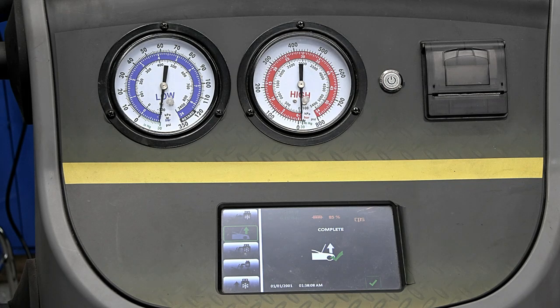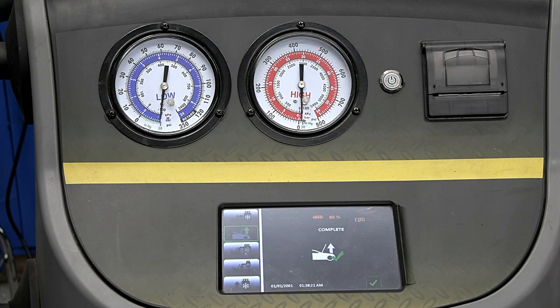Yeah, there's a couple. Is the CO2 better than traditional leak detectors, especially for detecting evaporators? Yes, CO2 is a smaller molecule, so it is way better. If you look at some of the videos I've done in the past, even in a class, I remember one where the guy's evaporator and his condenser were bad, and the detector did not pick it up, but CO2 did.